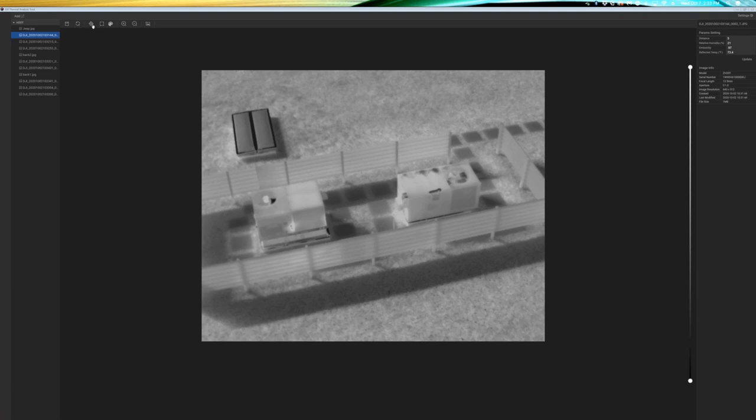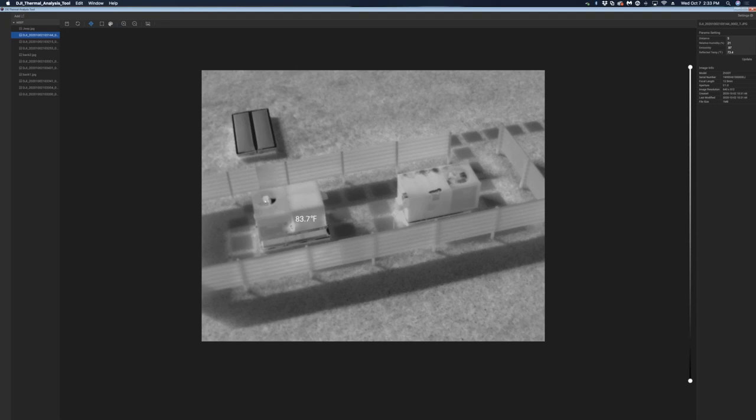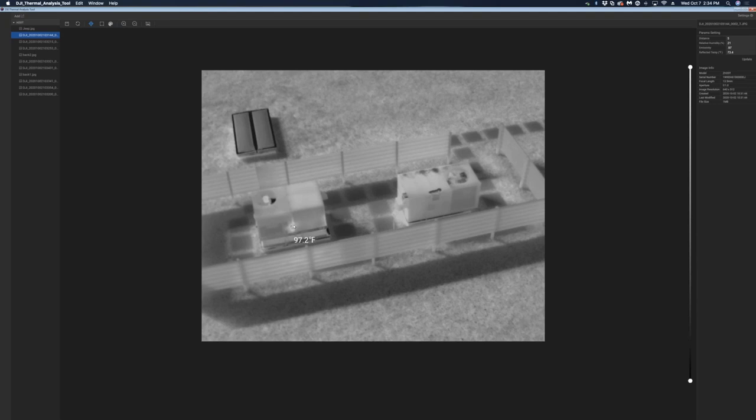So let's go up to the top here, and we'll select the first tool, which is the spot meter. And as I drag this around, we can see different spots. It's going to be really cold down on the bottom because it's an air conditioner. It should get down somewhere around, yep, around 40 degrees. That's what I would think. And the hottest points are going to be these motors up here, probably around 95 degrees or so. And if I just want to drop a spot there, now it's going to save that.